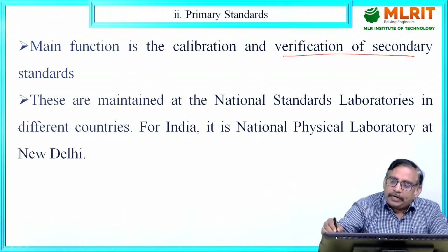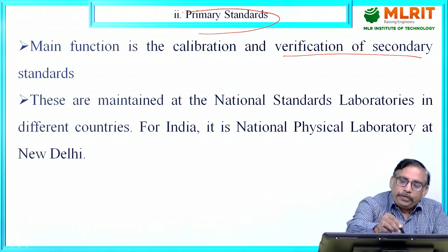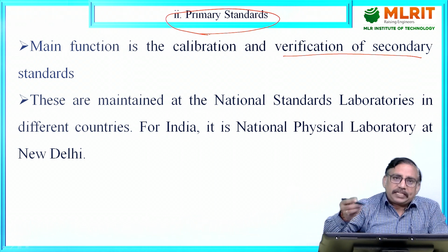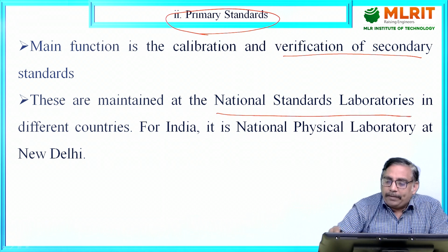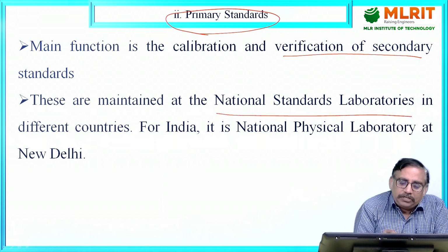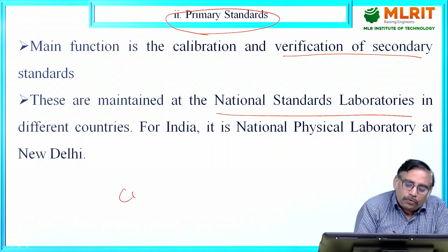So these primary standards will be used to check and verify the secondary standards, which will be on the second slide. And these are maintained at a national standard laboratory. So primary standards are restricted to particular countries only. It is not internationally recognized.